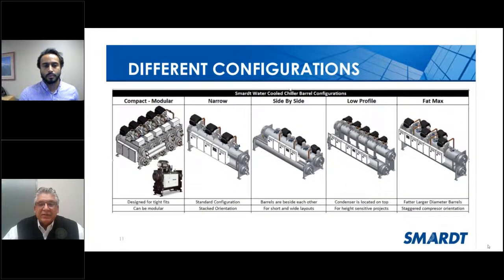If you look at the modular arrangement, the term modular chiller has a lot of different meanings, right? A compact modular, the one to the left there, is multiple small tonnage machines in a parallel type of arrangement, for an application where you may have a certain tonnage now and want to add additional tonnage as the building gets built out or as they add additional square footage. Also for retrofit applications where you've got a large machine, and you've had to cut it up, let's say, to get it out of the mechanical room. Now these machines go in pieces, a much smaller platform, and you can add tonnage as well.